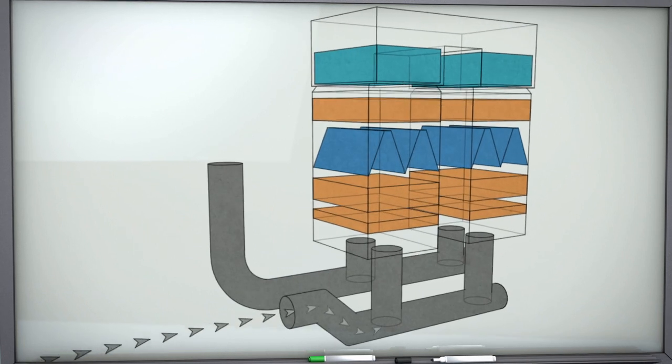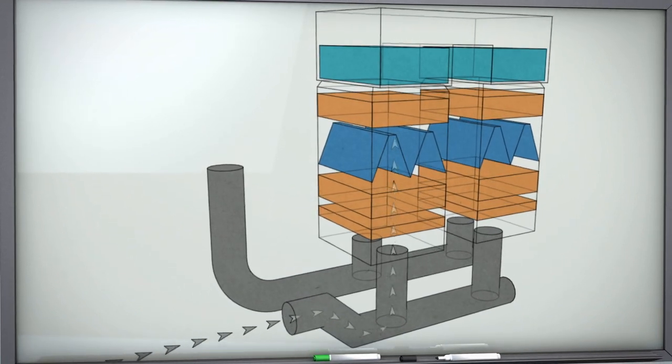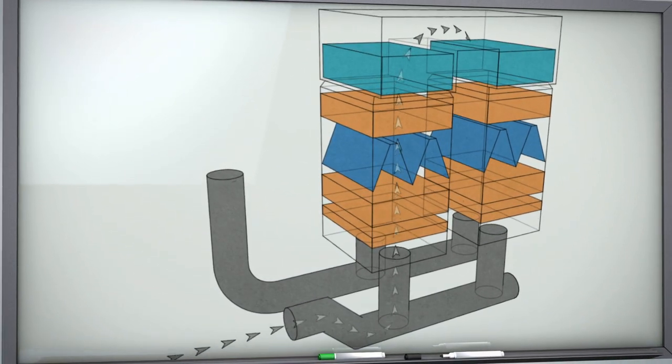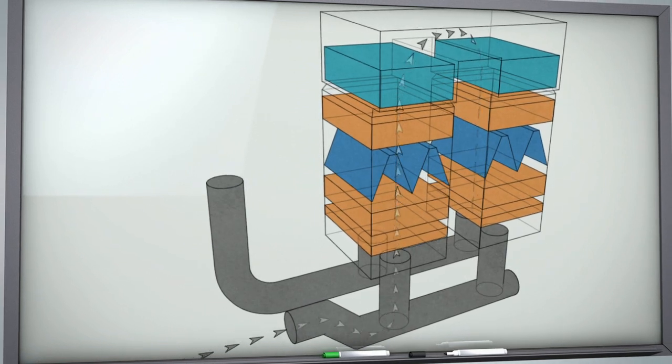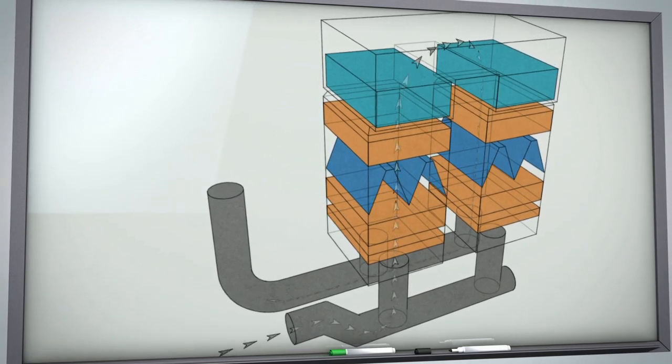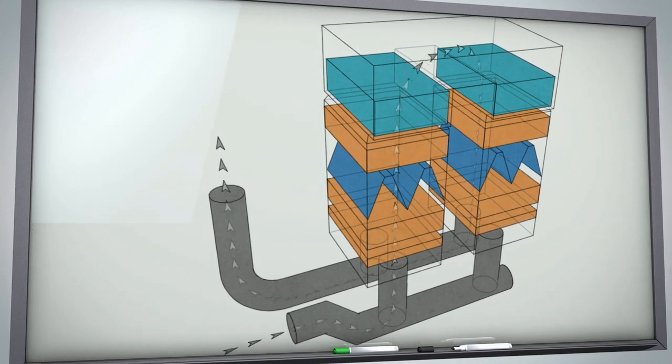The process begins by drawing the exhaust stream into the regenerative catalytic oxidizer. As the stream enters the RCO, it will pass through the first of a series of heat exchangers that house ceramic heating material.